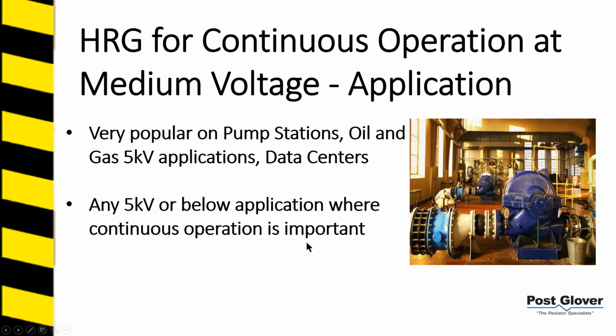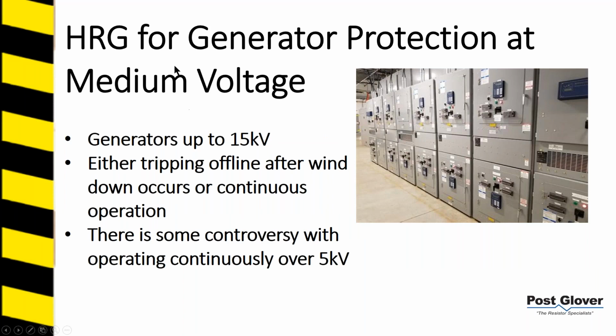So I guess the main message is it's doable. The question is, besides what we've already gone over, there are some design considerations. So HRG for generator protection, I'd say this is more common above 5 kV. Honestly, probably overall, it's more common than the continuous operation of HRG. But the idea is that you want to protect your generators from stator faults, essentially. We'll talk about that in a second. Sorry about that. Okay, so you're either tripping offline after the wind down occurs or continuous operation. So those are your options.